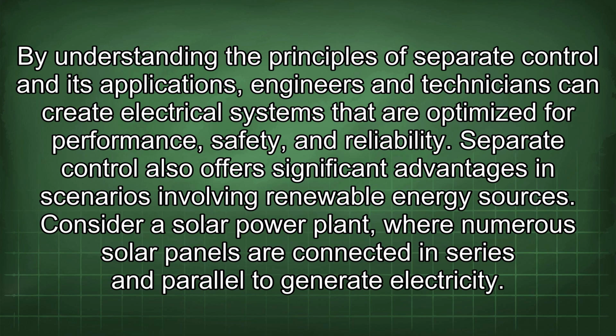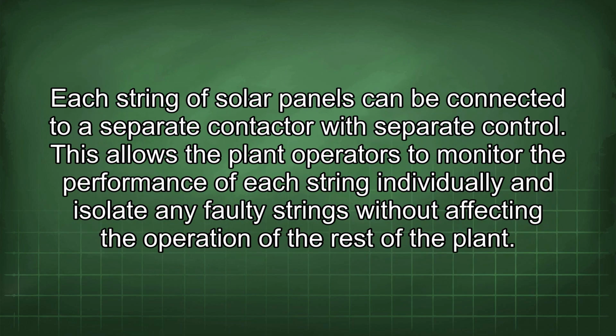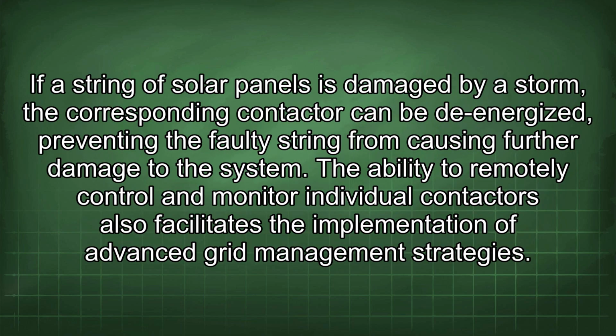Separate control also offers significant advantages in scenarios involving renewable energy sources. Consider a solar power plant, where numerous solar panels are connected in series and parallel to generate electricity. Each string of solar panels can be connected to a separate contactor with separate control. This allows the plant operators to monitor the performance of each string individually and isolate any faulty strings without affecting the operation of the rest of the plant. If a string of solar panels is damaged by a storm, the corresponding contactor can be de-energized, preventing the faulty string from causing further damage to the system.